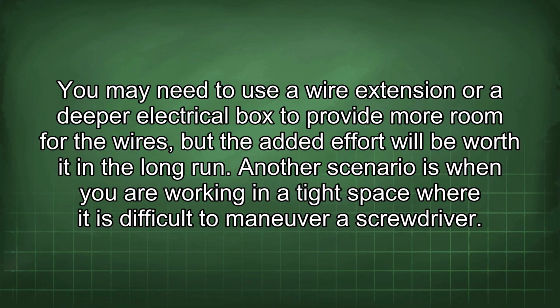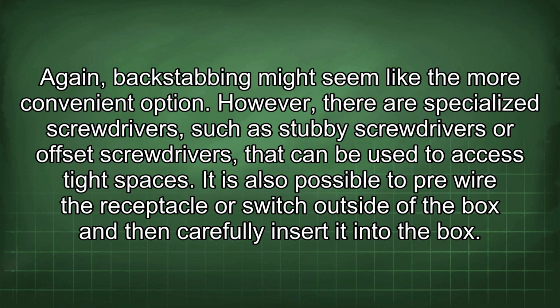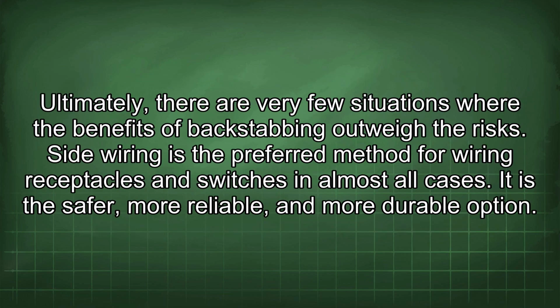Another scenario is when you are working in a tight space where it is difficult to maneuver a screwdriver. Again, backstabbing might seem like the more convenient option. However, there are specialized screwdrivers, such as stubby screwdrivers or offset screwdrivers, that can be used to access tight spaces. It is also possible to pre-wire the receptacle or switch outside of the box and then carefully insert it into the box. Ultimately, there are very few situations where the benefits of backstabbing outweigh the risks.